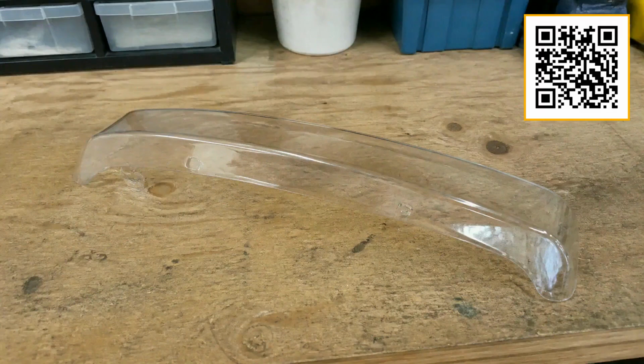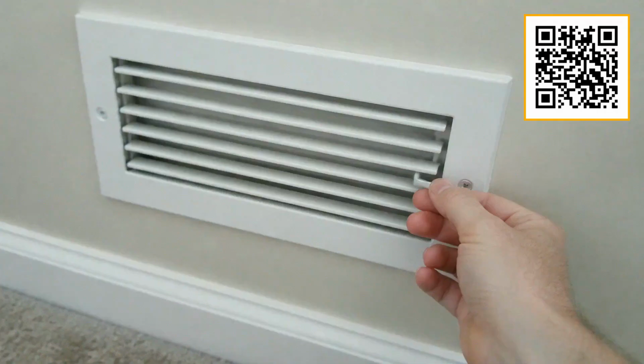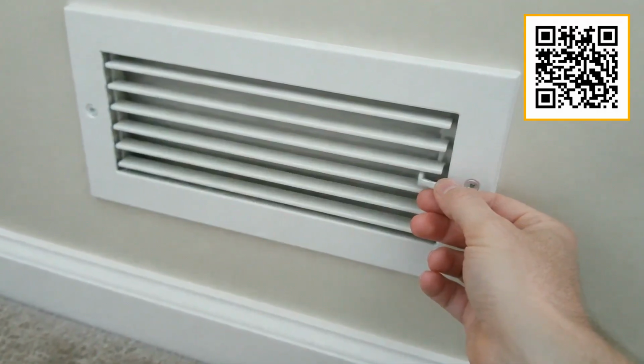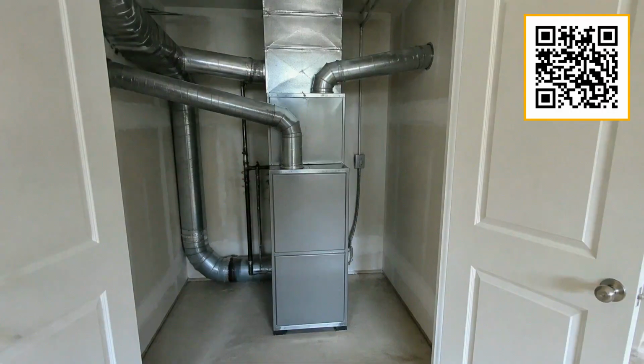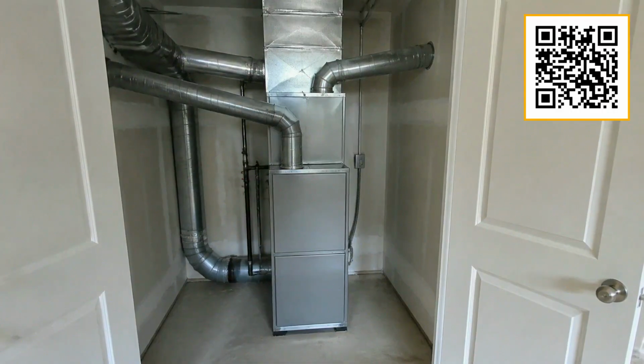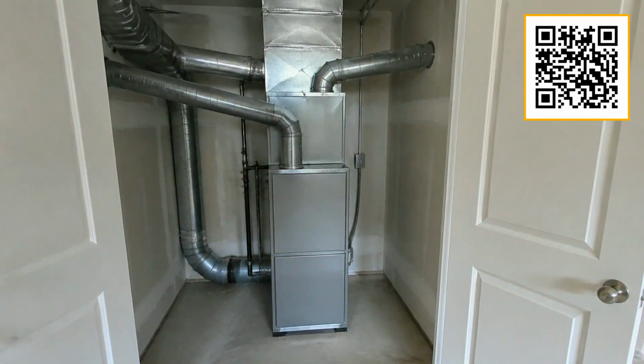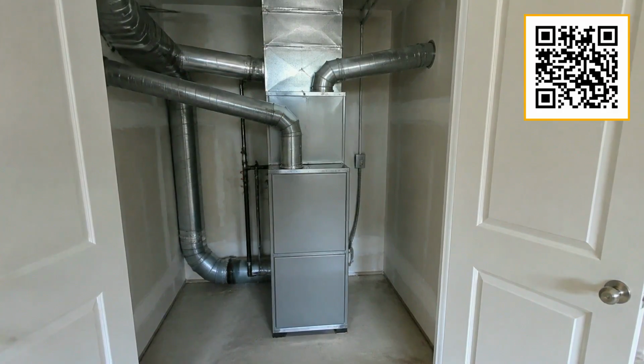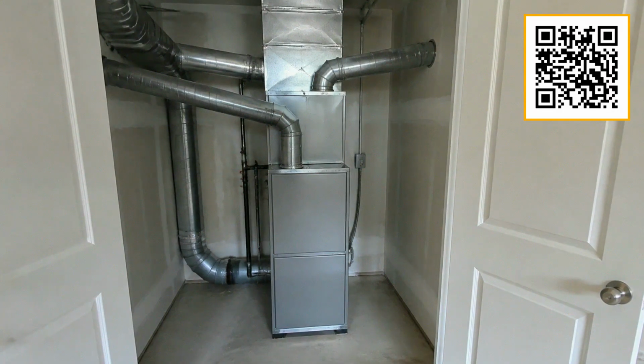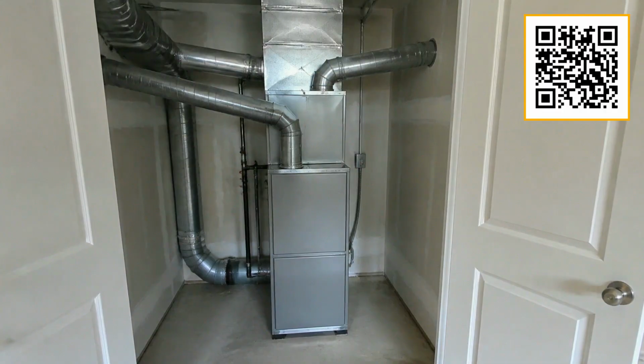There is no gadget to sell you here, no vent deflector, no magic register cover, no device that makes closing a vent safe. The fix is to stop doing the thing that is causing the problem. Your system was engineered with every vent open. Honor that, and it will serve you reliably for years longer than it otherwise would.